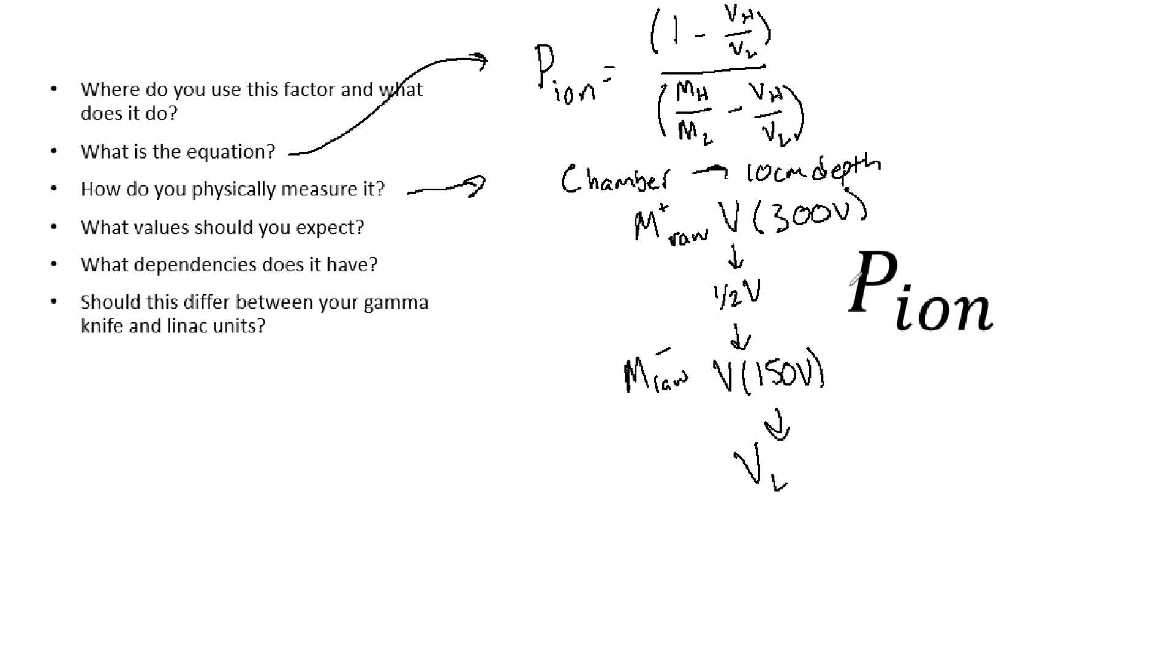So now what values should you expect? First of all, your P ion must be less than 1.05. Otherwise, you need to find a new chamber.